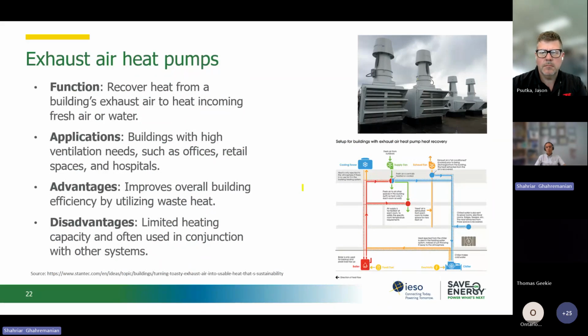Now we go to the exhaust air heat pumps, and these are basically a heat recovery system from the exhaust air. Typically the exhaust air is connected to the roof, and then we just dump it outside. But there are many projects that I saw where they install these exhaust air heat pumps, and basically they recover the heat from the exhaust air. So this is a really good recovery system, and it incorporates the heat pump mechanism to capture the heat. It can operate on exhaust air capture and do the heat exchange, and then bring that heat either for preheating during the winter season, or for water heating in the summer season as well.